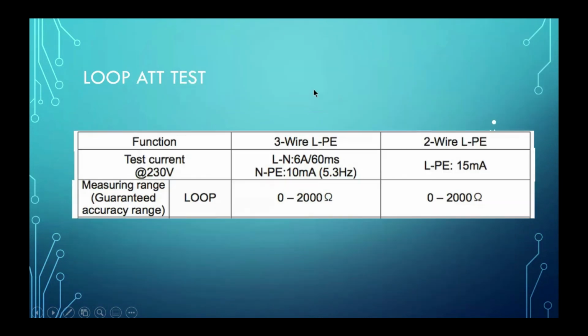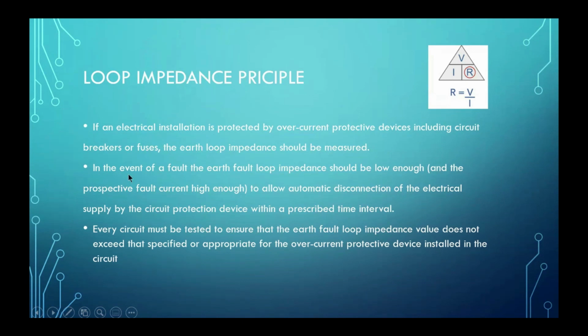Okay, understand? So in the second point here, we mentioned if a fault happens, the fault loop impedance should be low enough. It means this resistance must be low enough. What does this formula show? R is inversely proportional to I. Meaning when resistance or impedance is low, the current is high. You all know the mathematics.